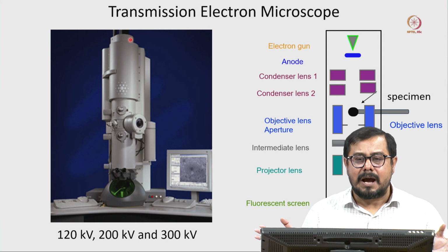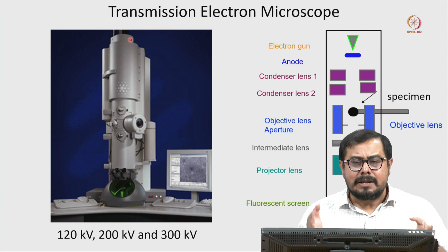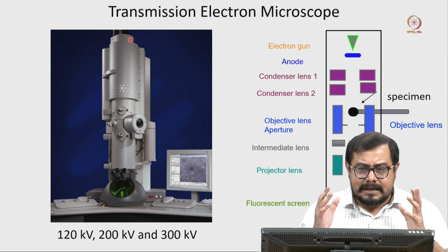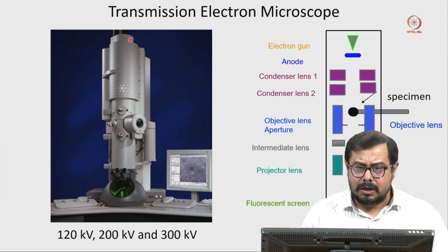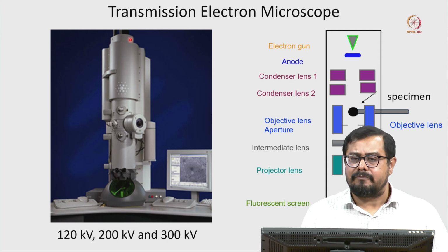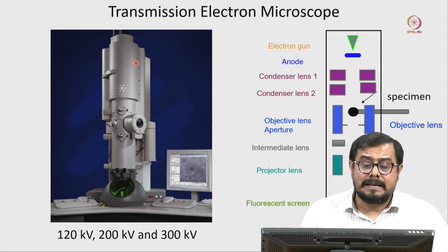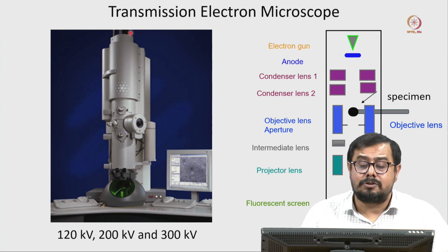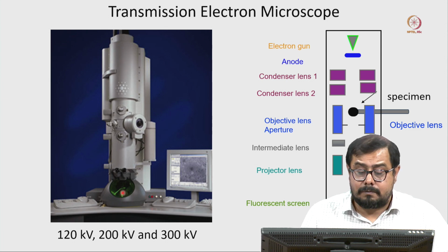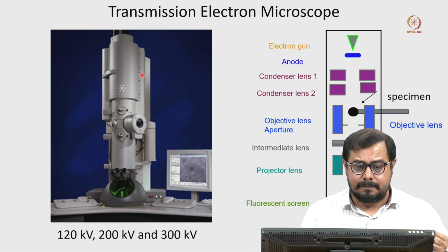It will interact with other molecules or atoms or air and it will deflect, and you will get only noise. It cannot generate a good amount of scattered electron beam to give us a good image. That is the reason we cannot see the electromagnetic lens or gun or other parts, because it is entirely under a high vacuum. Not only that, even our filaments are very delicate and very expensive.